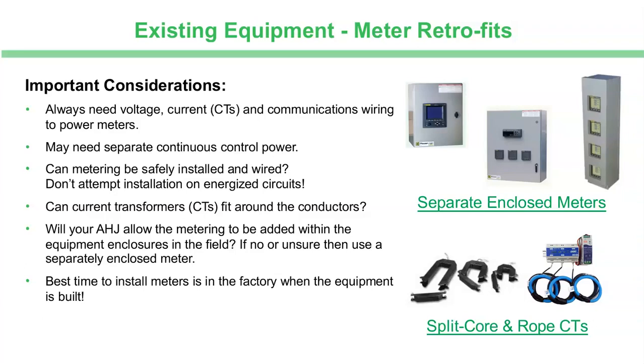When you're looking at the voltage supplied to that meter, you have to power the meter as well. So a common practice is to simply use the voltage input from the circuit you're monitoring for control power to the meter itself. In critical applications, you often want to avoid that, and you want a separate continuous control power source. If there should be a disruption in power, you want to be able to have the meter online and be able to communicate and be able to see what's going on remotely. And if your meter is powered by that voltage, it'll simply go offline. The way that that's typically done is through UPS power, and the UPS can either be existing or in these enclosures, a separate small UPS can be provided for that continuous control source, but it's very important to think about that.